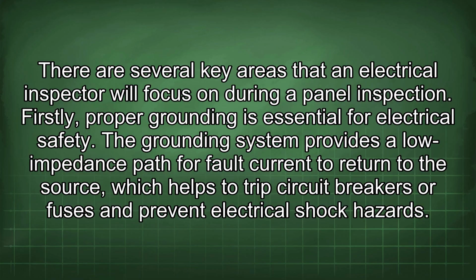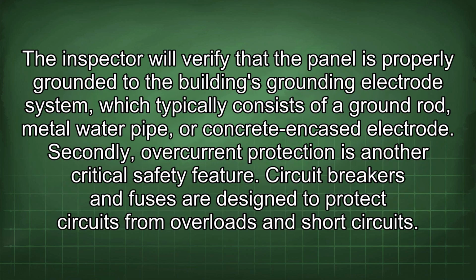Firstly, proper grounding is essential for electrical safety. The grounding system provides a low impedance path for fault current to return to the source, which helps to trip circuit breakers or fuses and prevent electrical shock hazards. The inspector will verify that the panel is properly grounded to the building's grounding electrode system, which typically consists of a ground rod, metal water pipe, or concrete encased electrode.